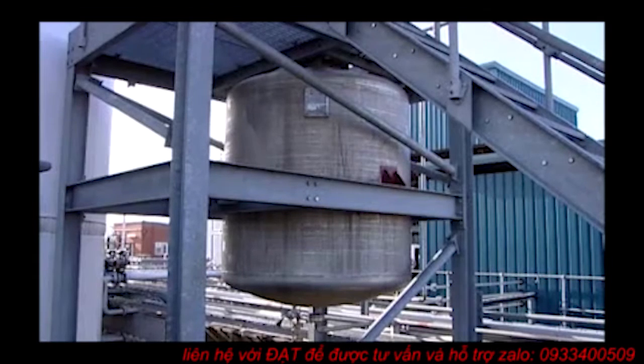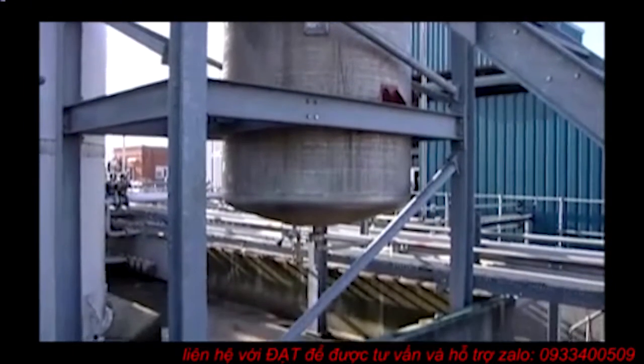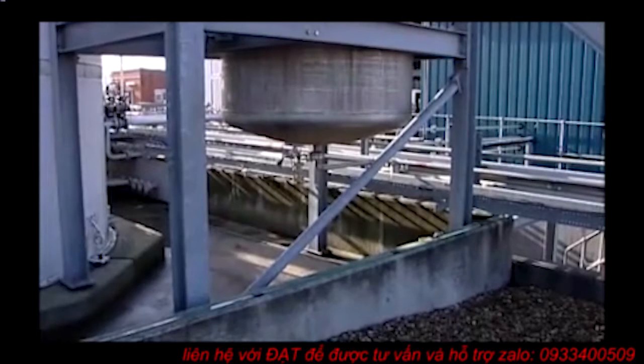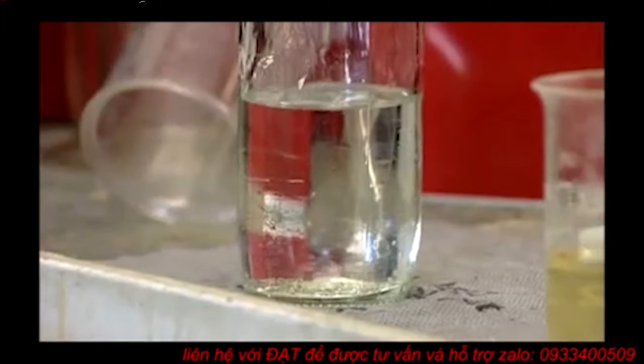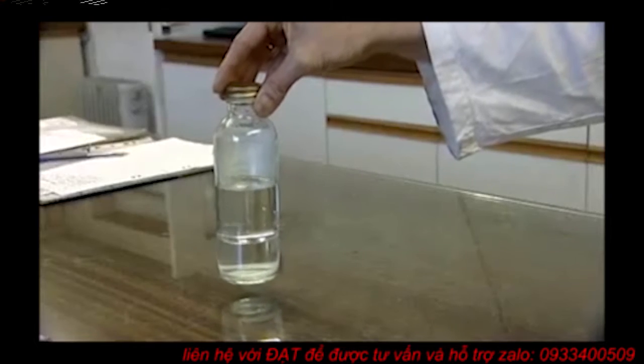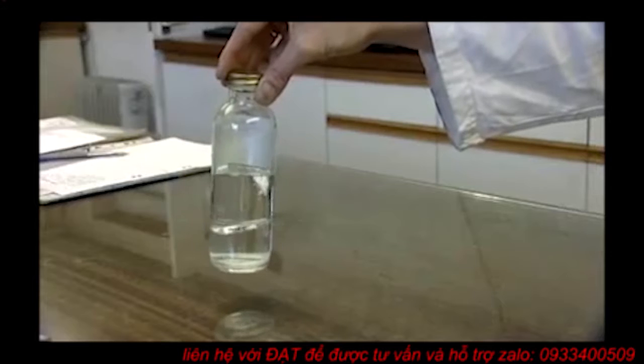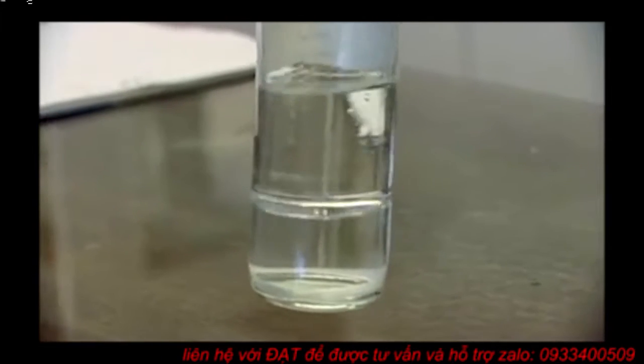Dispersing operations can be particularly hazardous in view of the extremely high rate of charge generation when particulates are present. High charge rates can also occur when liquids containing non-miscible components are mixed or agitated. With poorly conductive liquids, the charge accumulation can cause sparking in the vapor space to an exposed agitator blade in a mixer or to a filling pipe.